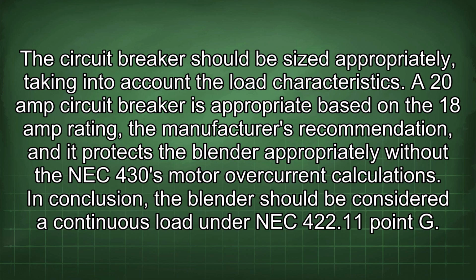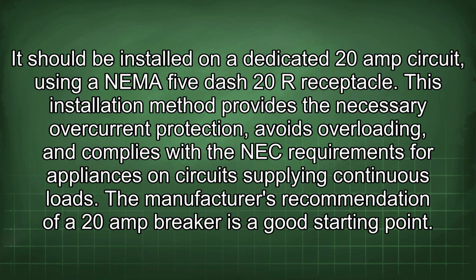In conclusion, the blender should be considered a continuous load under NEC 422.11.g. It should be installed on a dedicated 20 amp circuit, using a NEMA 5-20R receptacle. This installation method provides the necessary overcurrent protection, avoids overloading, and complies with the NEC requirements for appliances on circuits supplying continuous loads. The manufacturer's recommendation of a 20 amp breaker is a good starting point.